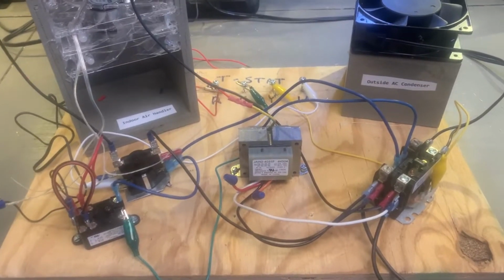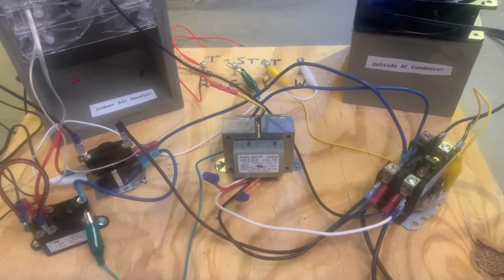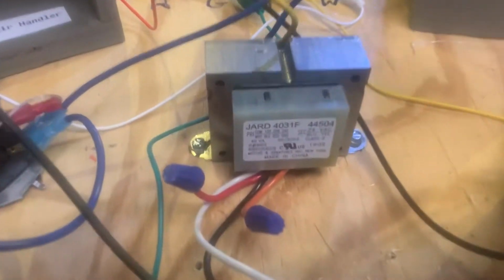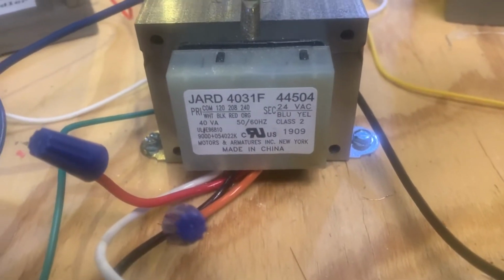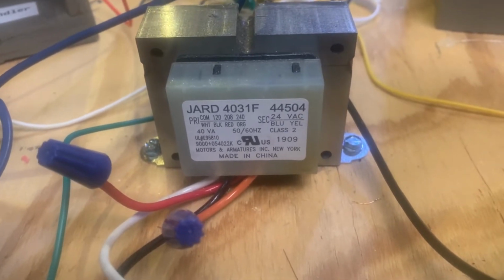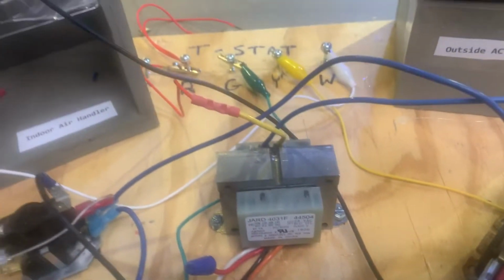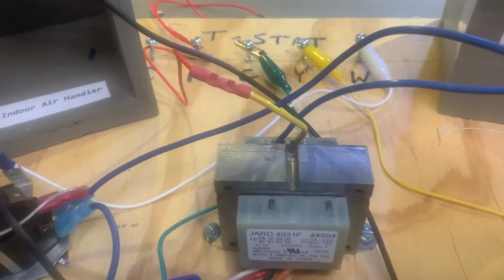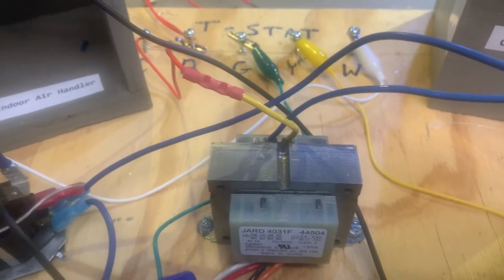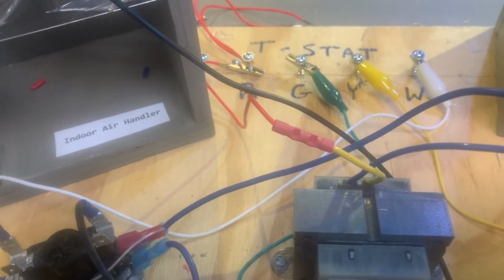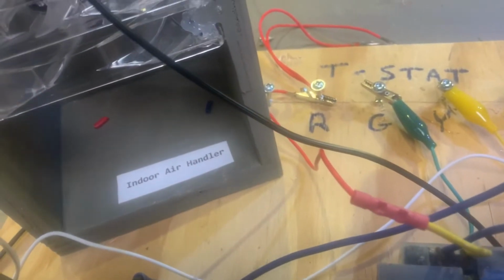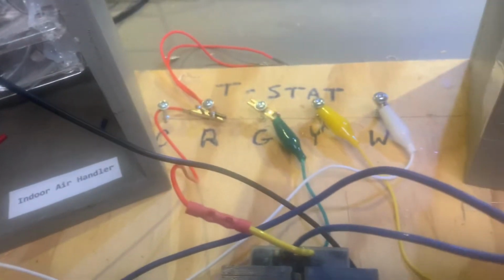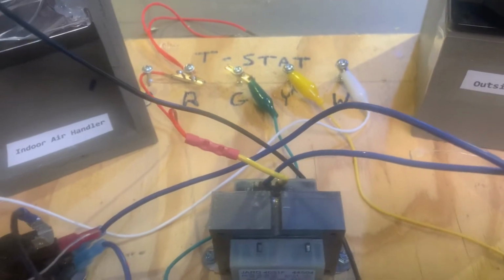Okay, we need 24 volts to operate all of our relays, and that's where this transformer comes in. We've got 120 volts going into the primary side, and then on the secondary side we've got 24 volts coming out, which is the yellow and the blue. And I've just got the yellow, I turned that to red, and then I've got it up here on red at the thermostat, so it'd kind of make more sense.